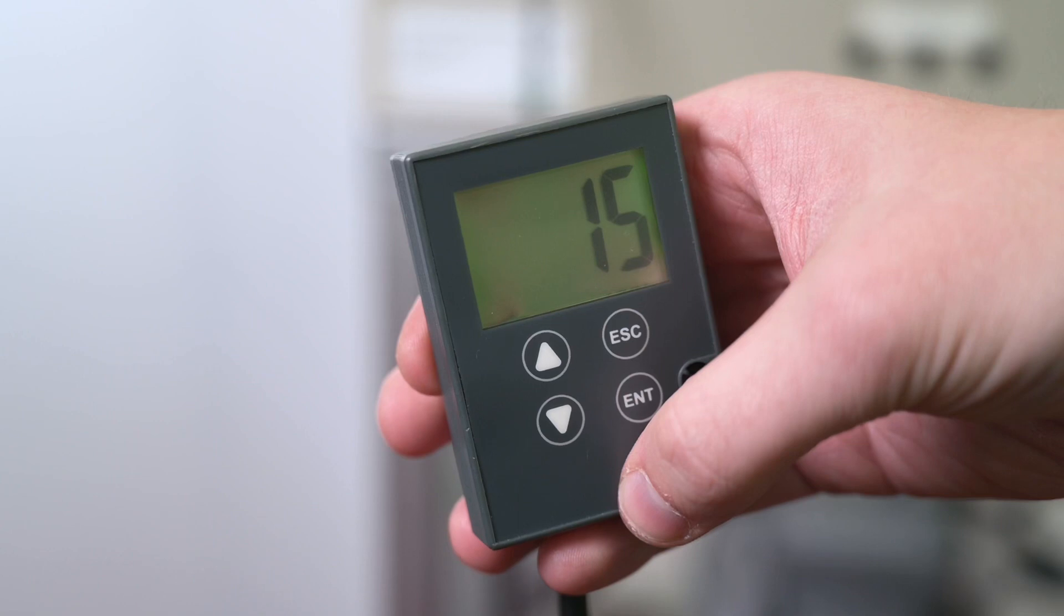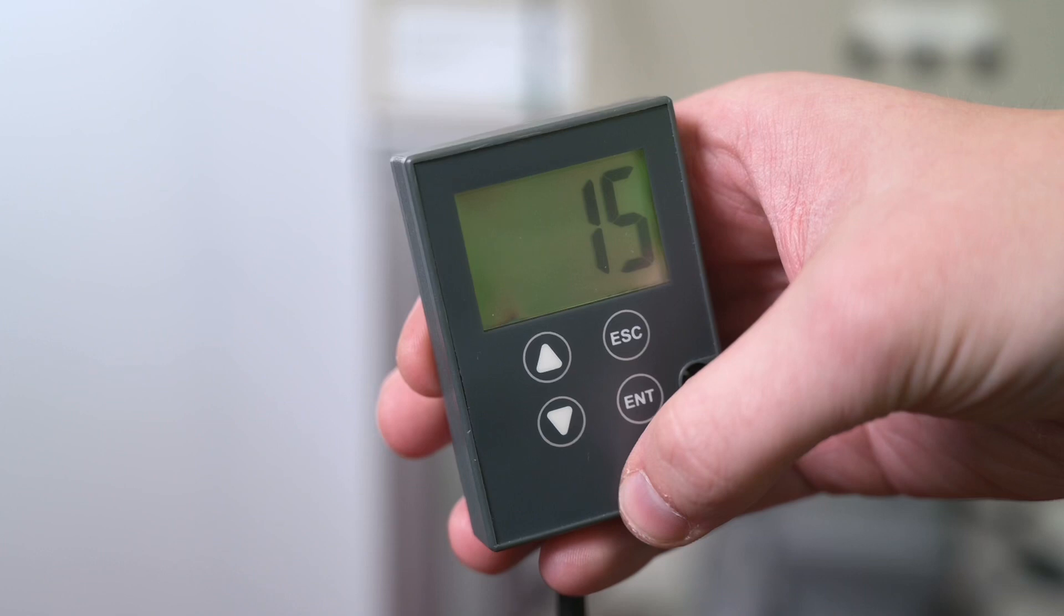The soft stopping by control of torque D allows us to set a time between 1 and 60 seconds to completely stop the motor. By default, the value is 15 seconds.